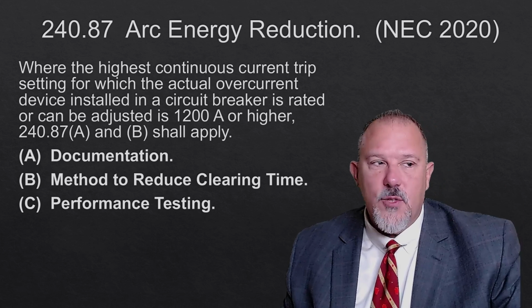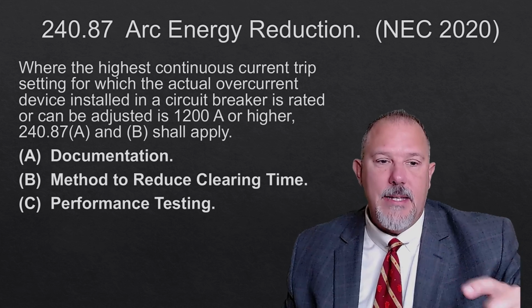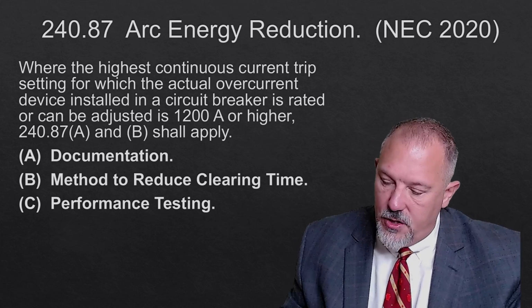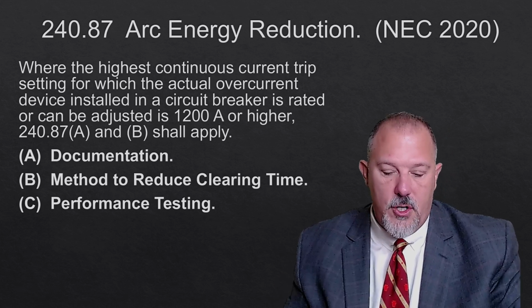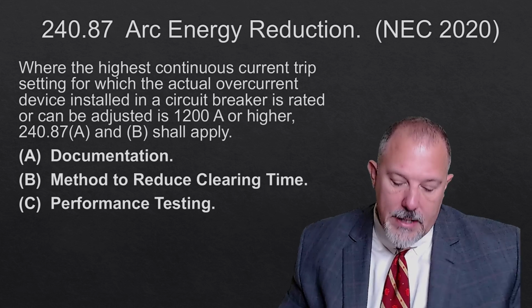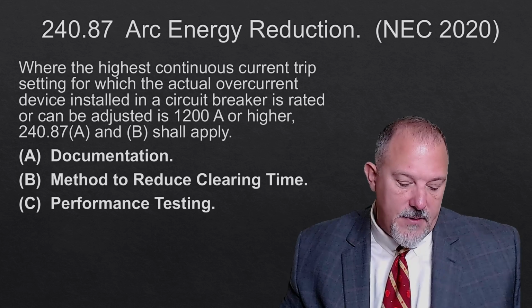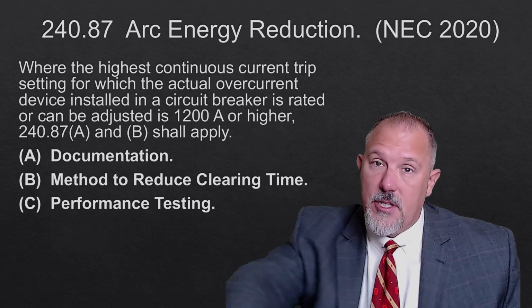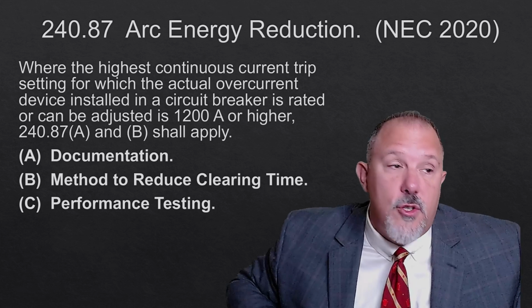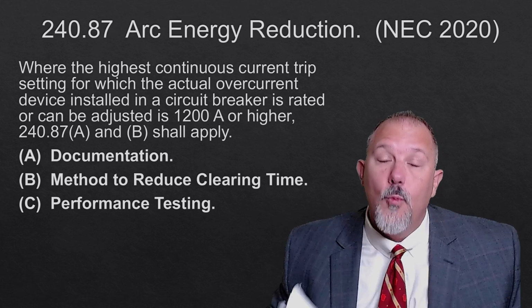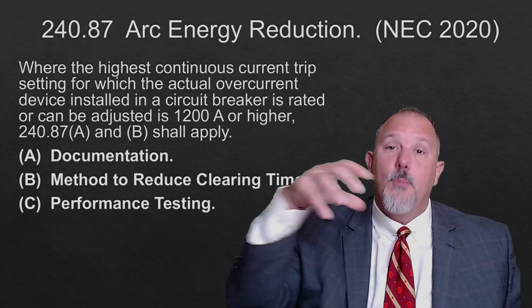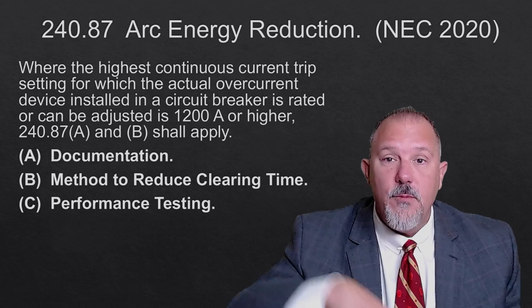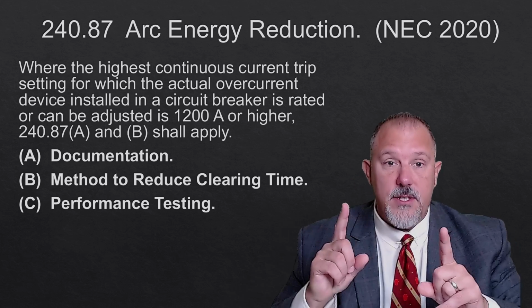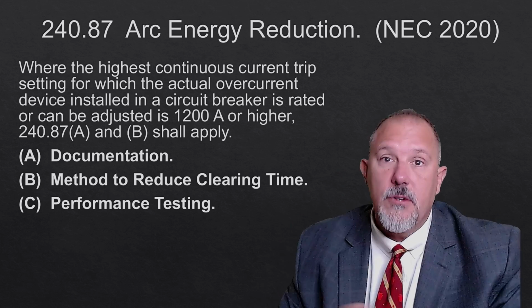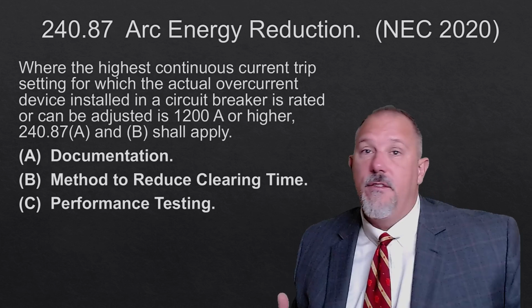So A tells us we need to have documentation. B tells us the methods. If we look at 240.87, so grab your code book, 240.87 gives us options, gives us 7 options. And the 7th option is an approved equivalent means, which opens the door for new technologies. We realize that we can protect equipment and we can protect personnel. This is there to protect personnel from arc flash events.